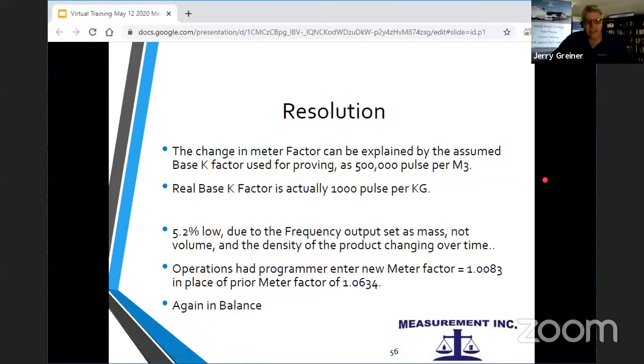The change in the meter factor was basically explained by the difference in K factors. They were using a K factor of 500,000, and that wasn't what was really there. They thought it was 500,000 pulses per cubic meter. Really, it was giving 1,000 per kilogram. When it first started and the density was really close to 0.500, or just a little higher, the 500,000 worked. As the density shifted, their number didn't work.